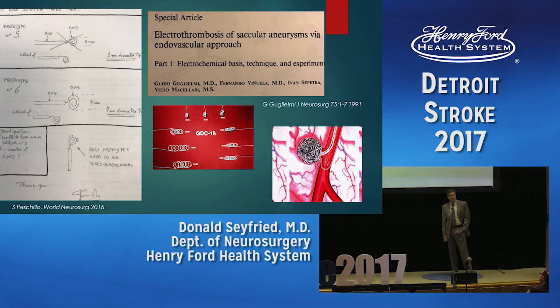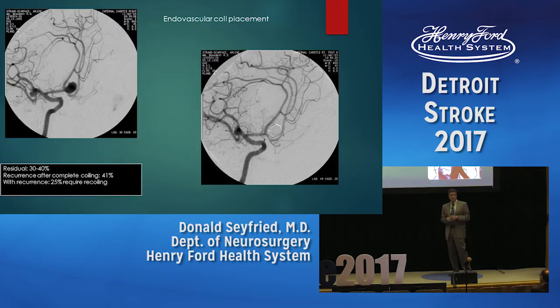The field was revolutionized in 1991 when Italian neurosurgeon Guido Guglielmi developed a platinum wire that was helical — wound very tightly. When passed through the catheter and released, it forms predetermined-diameter coils. In two dimensions they appear flat, but when released inside an aneurysm they form a three-dimensional basket structure that can occlude the aneurysm. It blocks about 30% of the aneurysm volume inside, and is meant to tamponade and eventually cause thrombosis — likely through disruption of flow rather than electro-stimulation alone.